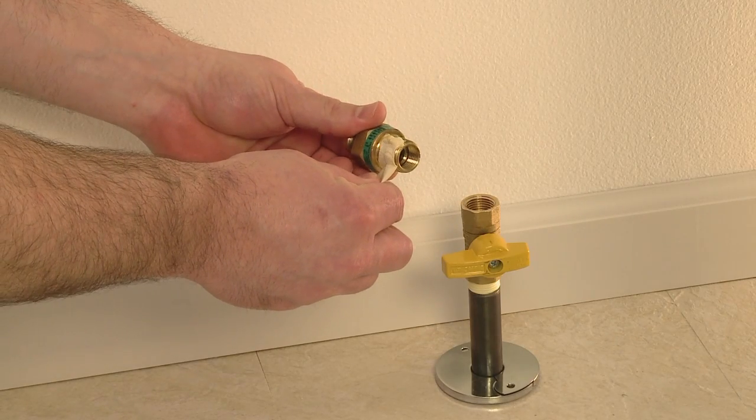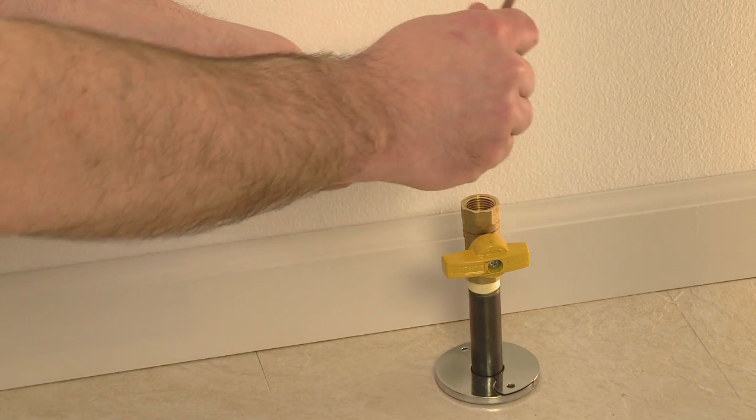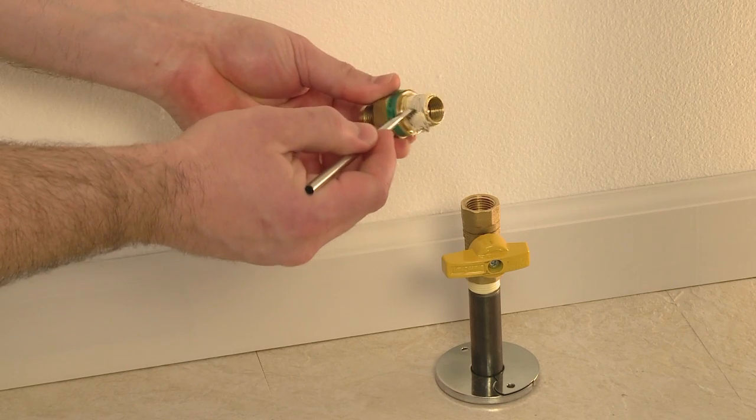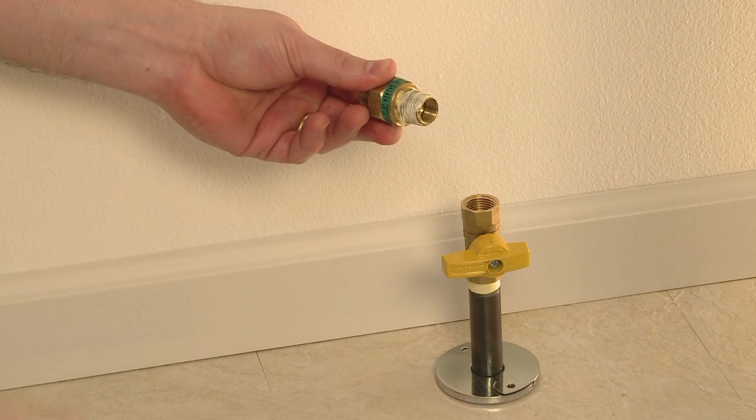Apply pipe thread sealant or yellow gas thread tape to the male threads of the excess flow valve. Remember thread sealant is only applied to the pipe threads. No sealant should be used on the flare threads of the fittings or inside the nuts of the gas appliance connector itself.